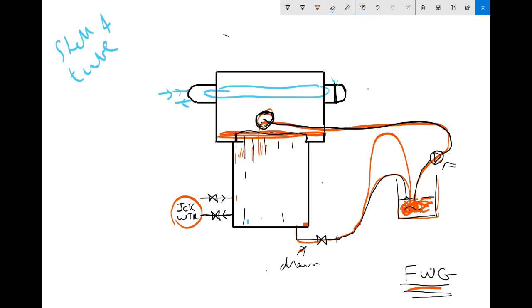Even for the condenser side. Now for the evaporator, I have told you all, this is the method. For the evaporator side, there is another method which people use: they fill water inside without recirculation, without any pumps. They just fill water here, add chemical inside, keep it stagnant and turn on the heating. After some time it will clean, but the efficiency is not as good as when you do it with recirculation with the pump.